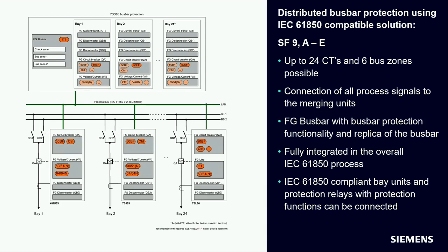We are here talking of a distributed system, which means the process signals of the circuit breaker, the disconnectors, and the current transformers are connected to the merging unit and not directly connected to the 7SS85. The merging units are then connected by process bus to the central unit. In this case, the communication topology is drawn like a star connection. We will talk about the possible communication topologies for distributed busbar protection systems in our third session, also next year.